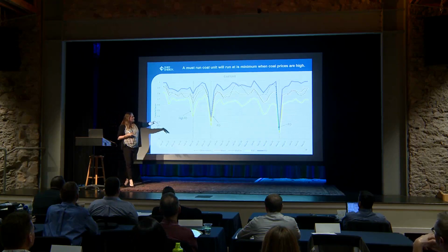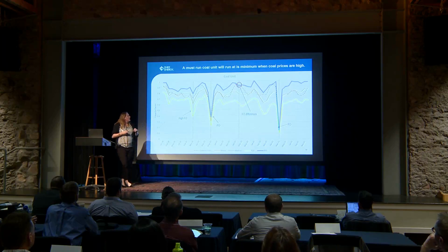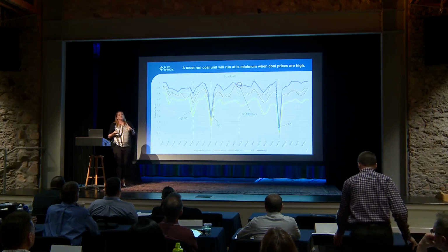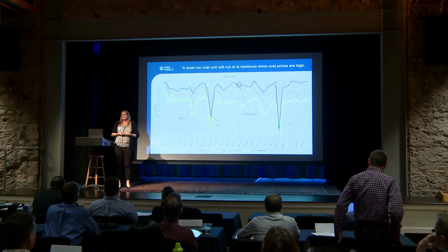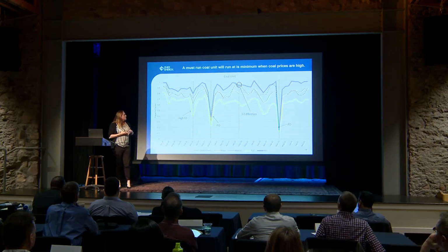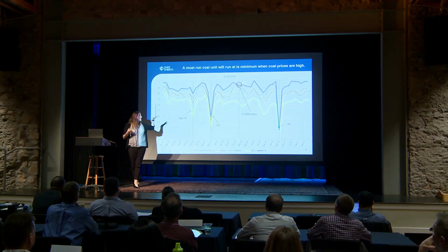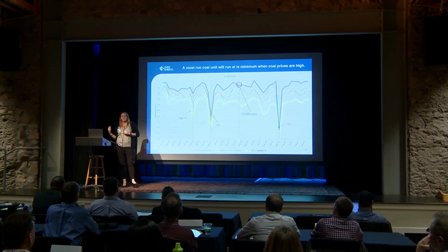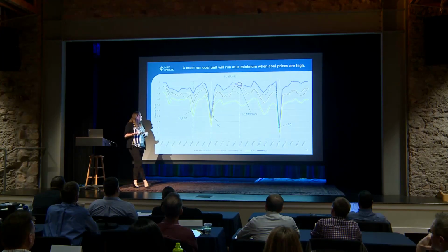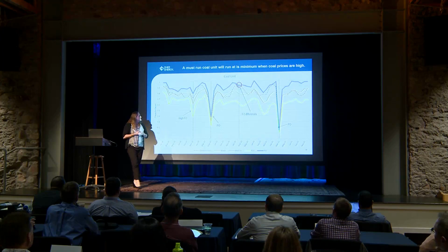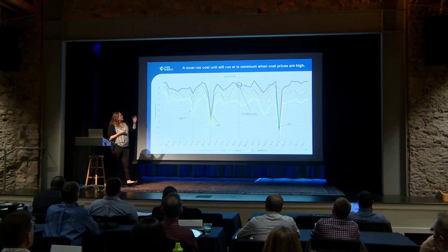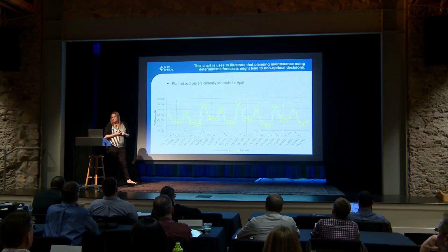These are some planned outages that are occurring. And then there's one point up here. Actually, I think there's a few of them in this plot. In our deterministic model, we model forced outages in not the best way. So in this specific case, I dug into what's going on in this month. Why is my deterministic higher than my P90? The forced outages were just a lot lower in your deterministic model in that specific month. So that was showing up in it crossing the P90 case.